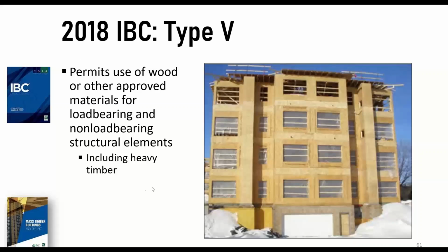In type 5, in this particular photo, we're illustrating a common pedestal or podium building. So 4/1 is a really common configuration for a fully sprinklered building in the IBC. More commonly associated with your R2, multifamily dwellings, which have to be residential and protected with sprinklers. So with real estate being as pricey as it is, instead of having a separate standalone parking garage, you're allowed to do a 3-hour horizontal separation, typically reinforced structural concrete or protected steel, with a fully sprinklered NFPA 13 sprinkler system in the garage area. And then that 3-hour horizontal separation cordons off the rest of the building above.